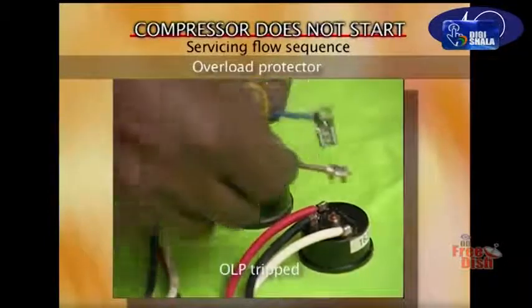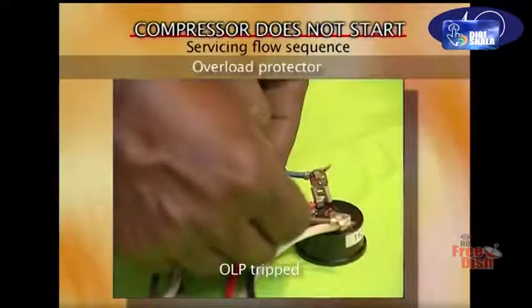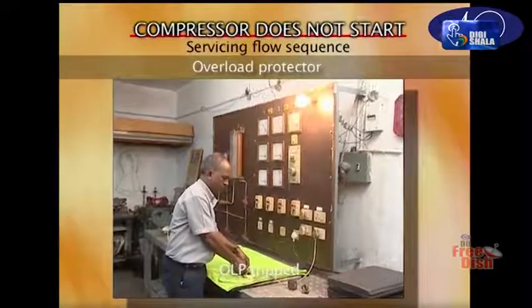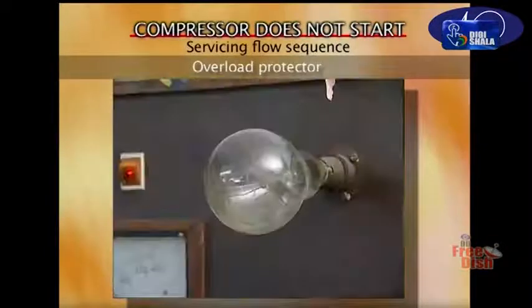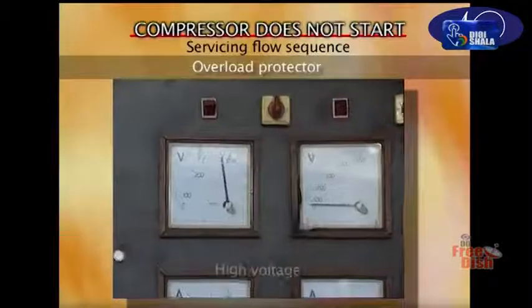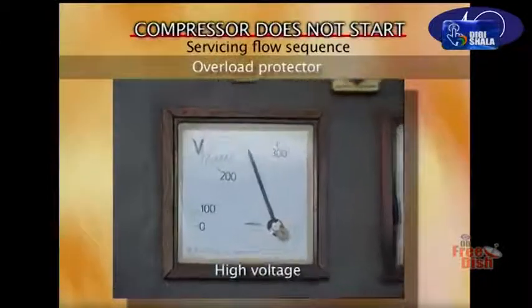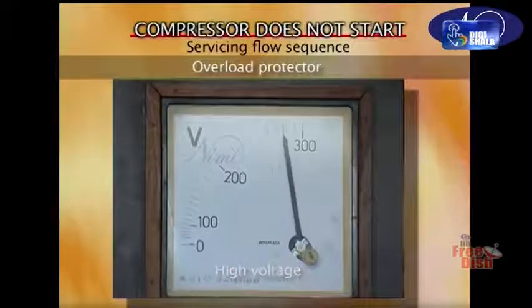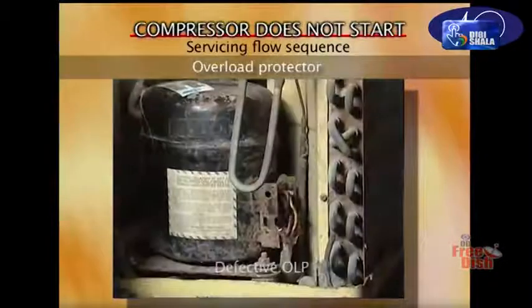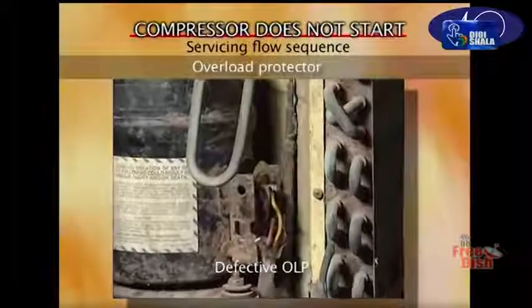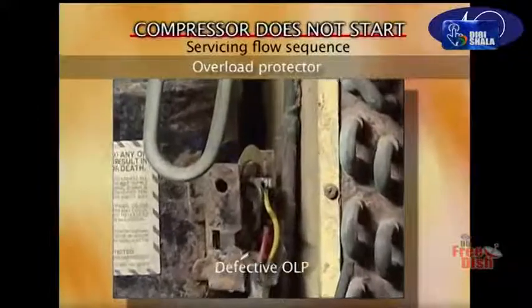The overload protector could have tripped. Or it could be a high voltage. Or the overload protector is defective.